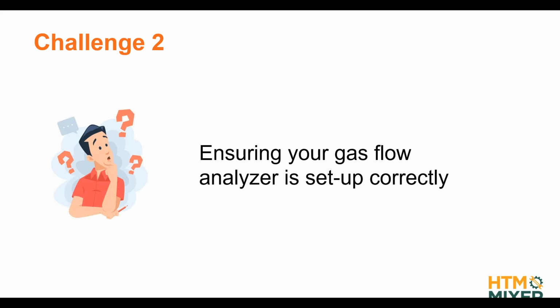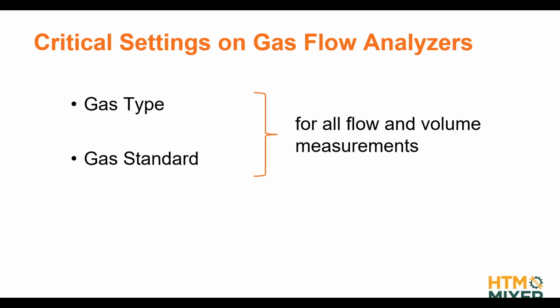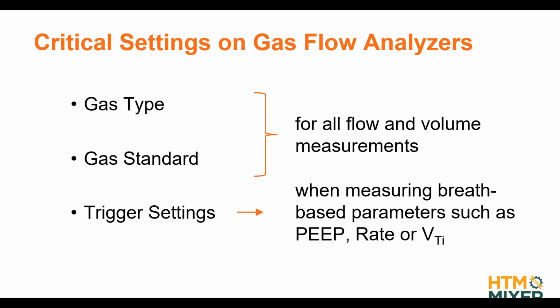So what are typical settings on gas flow analyzers? So the most important critical settings are gas type. Maybe you've heard about that. Gas standard. These two are actually crucial for all flow and volume measurements. And we'll talk about them in just a bit. Then maybe you've heard about trigger settings. Trigger settings is something different. They are used when we want to measure so-called breath-based parameters, such as PEEP pressure, you'll hear, or a respiratory rate, or tidal volumes of a ventilator.